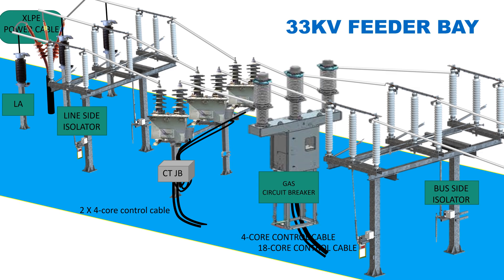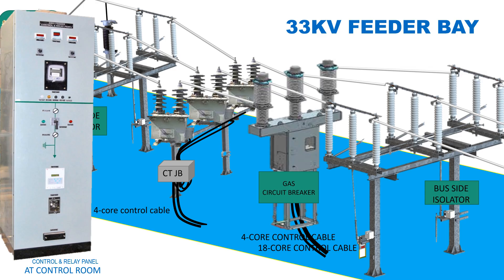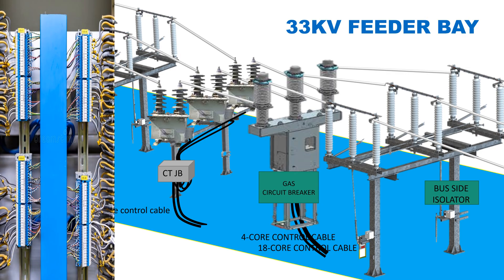In this picture, you are watching a 33kV feeder bay comprising two isolators — one at the main bus side and the other at the line side — circuit breaker number one, three CTs, LAs, and XLPE cables. Suppose all these have been erected but no wiring has been done. We shall now connect the current transformers with the control and relay panel, the circuit breaker with the control and relay panel, and also the AC/DC power connection to the circuit breaker mechanism box.